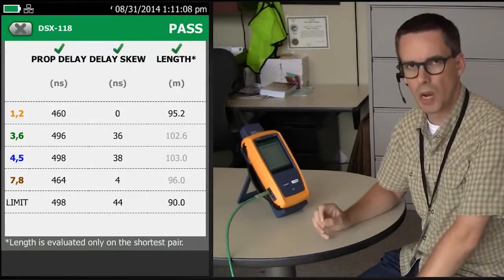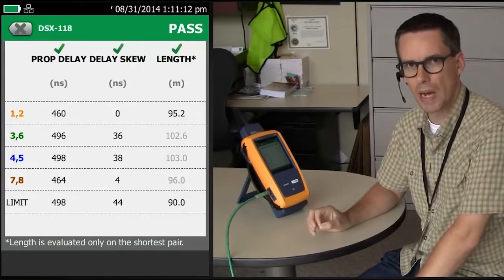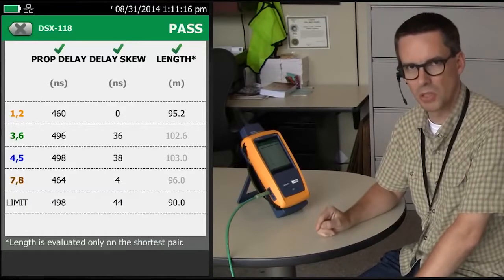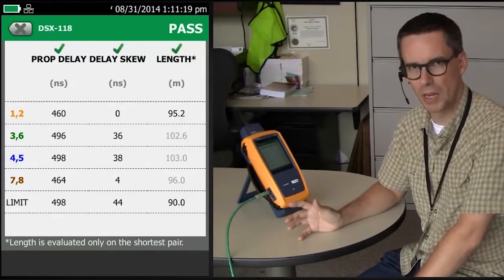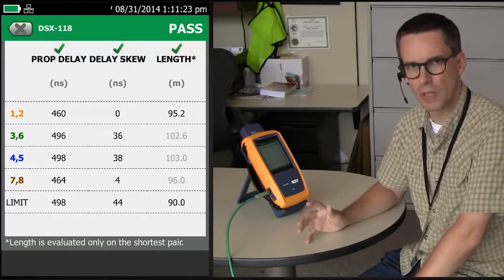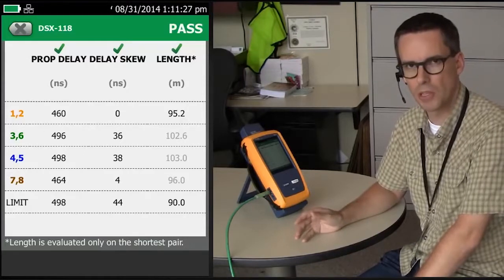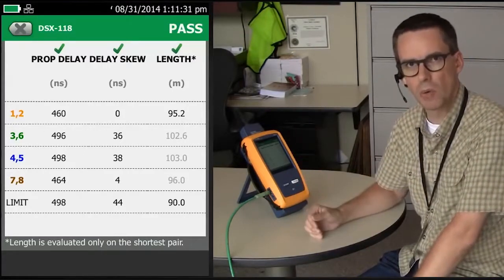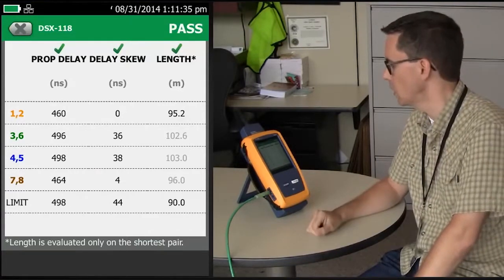And funny enough, when you go and do an ISO test, in ISO there is no pass-fail on the length measurement. That's not an excuse to go to 99 meters or 324.5 feet. But in ISO, that's exactly the same philosophy — if the length-dependent parameters like insertion loss and propagation delay are met, then it's okay. There's nothing wrong with the length being 95 meters or 312 feet odd.